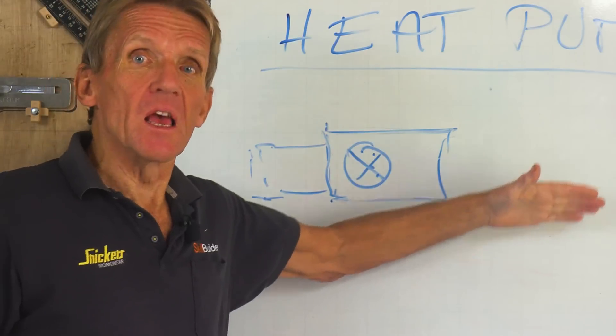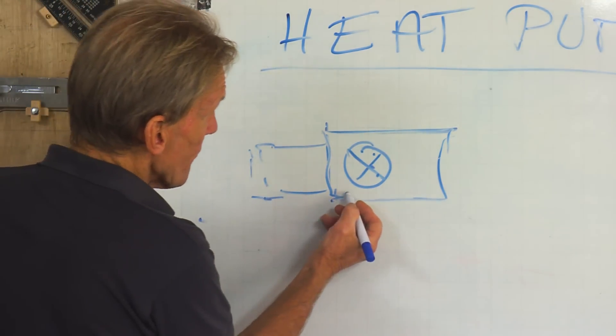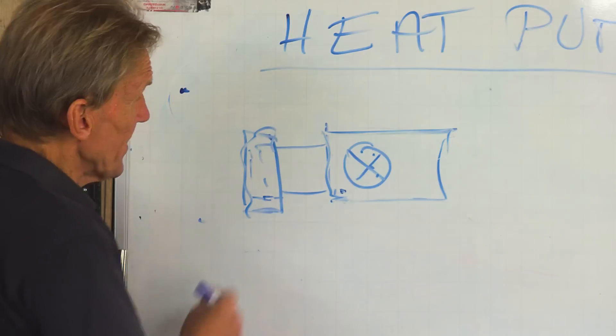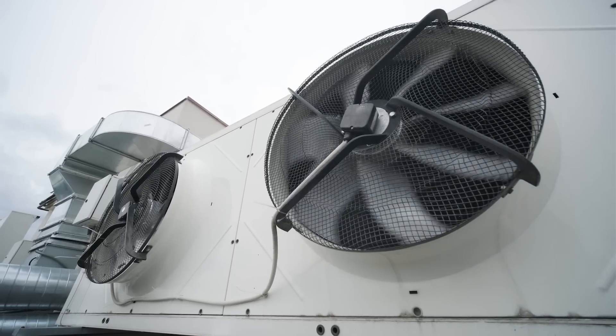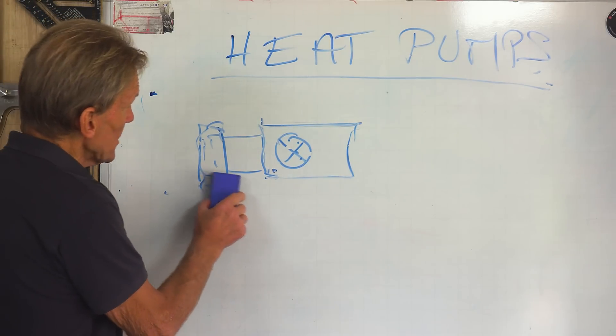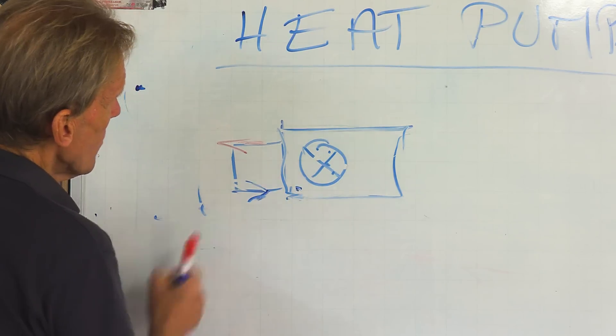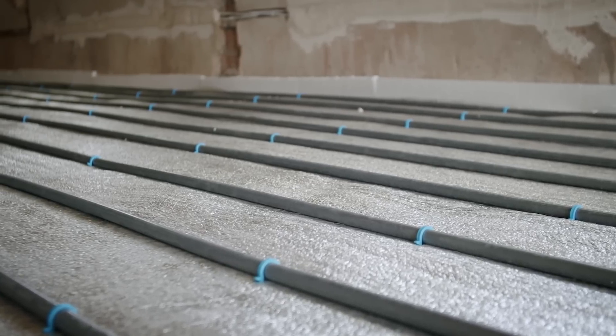There is a fundamental misunderstanding that comes up all the time. People think the refrigeration circuit goes outside and inside, with an evaporator inside — that is what we call a mini split, and there are millions of those around the world working as air conditioning systems. But the British model is not like that. The British model uses water coming out of that heat pump, returned as cooler water, going into the heating system and around either underfloor heating or radiators. It's a completely different principle to an air-to-air unit.